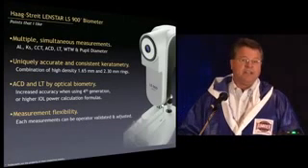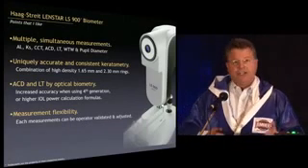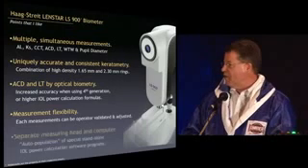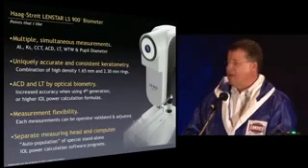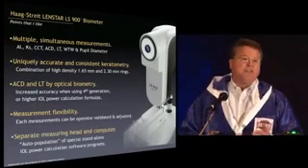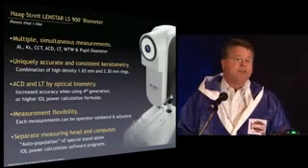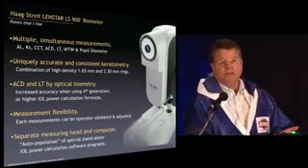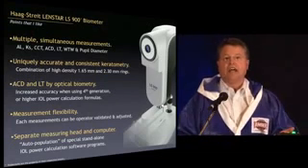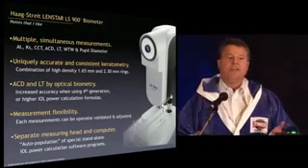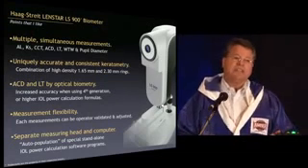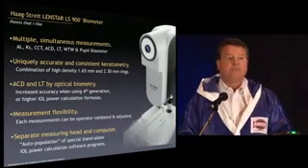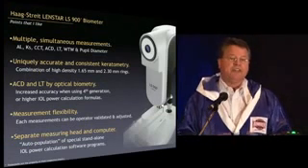Rather than just getting numbers that you're given, you can actually go in, move calipers, and get everything exactly where you want it to be. And the computer and the instrument are separate. This not only has the Holladay 2 formula, but it also has the entire Holladay IOL Consultant, plus access to any program you want to add, like the Olsen formula, perhaps some of the ray tracing technology.